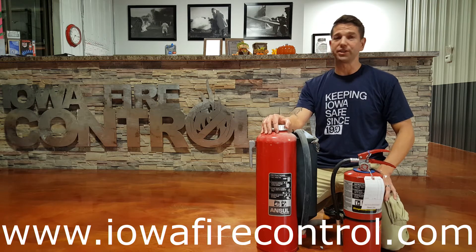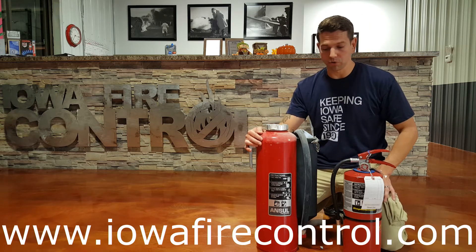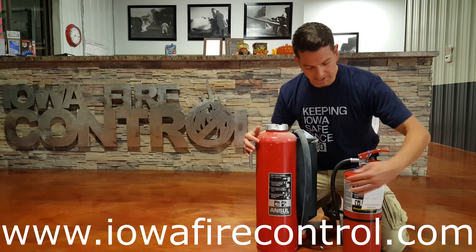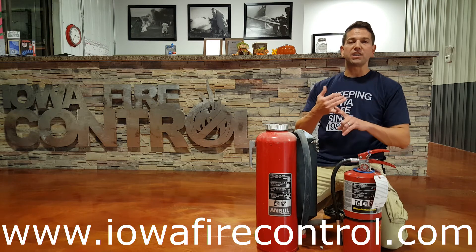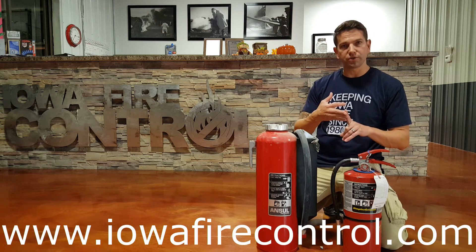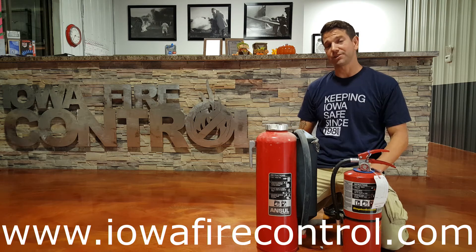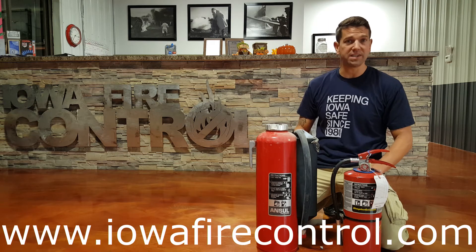With the cartridge operated, you can drop it from high above and you're going to be good to go. These shells are more durable. The nameplate right here on the front is way more durable than the nameplates on the stored pressure type. So if you're in heavy industrial, mining, forestry, recycling, or any type of large factory, and you want a fire extinguisher that's not going to have to be replaced every three, six, or nine years, choose this one.